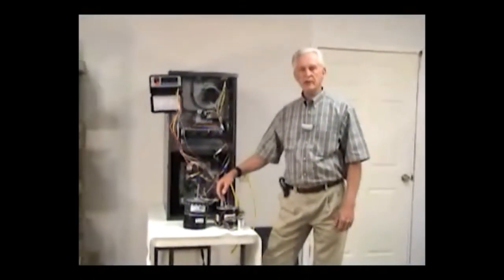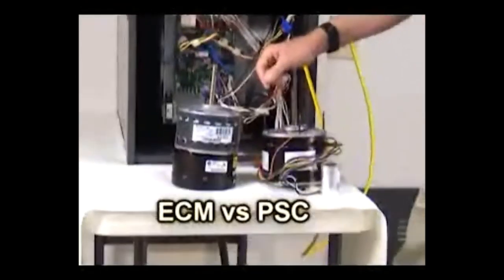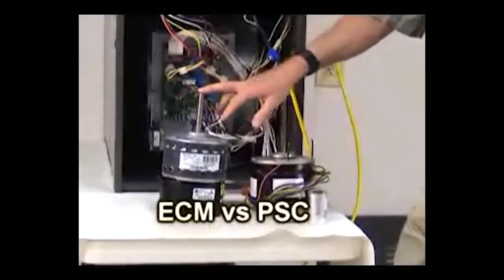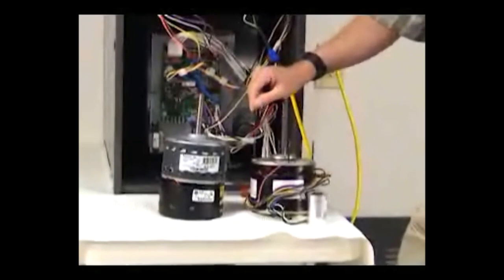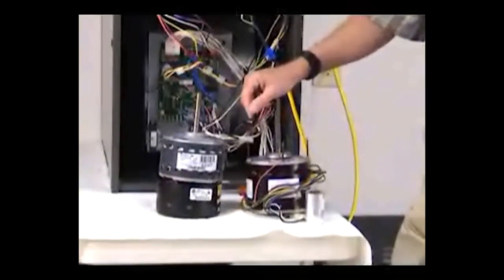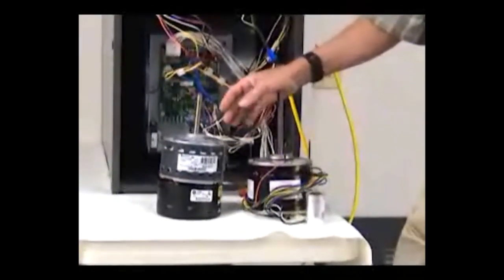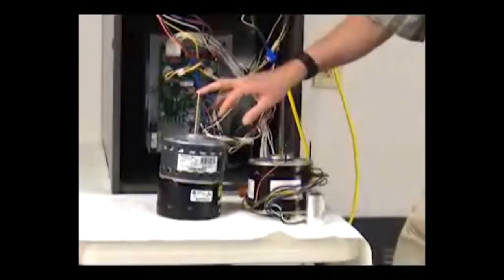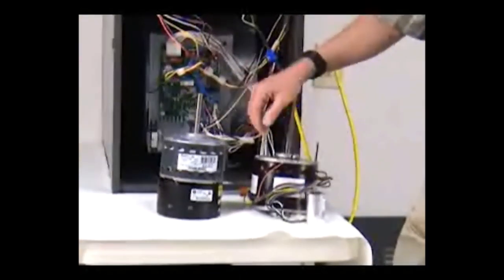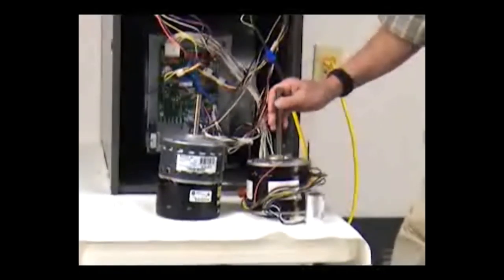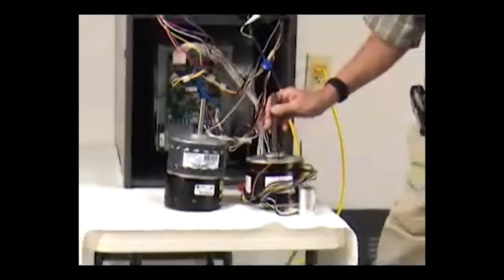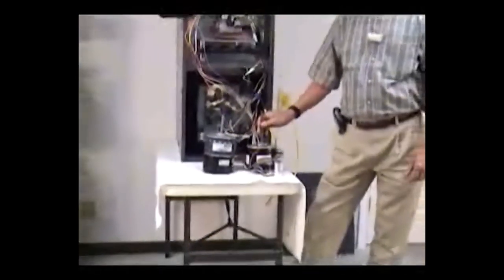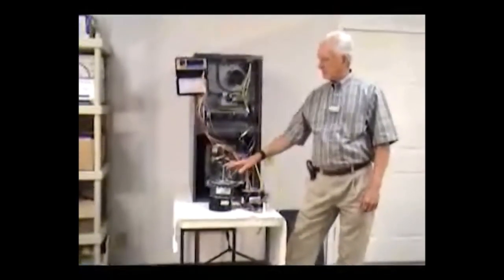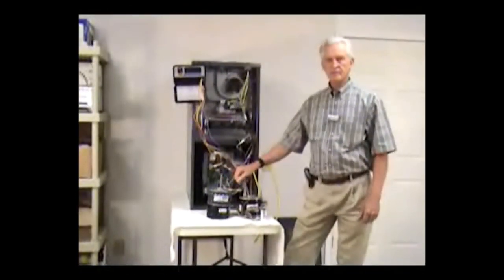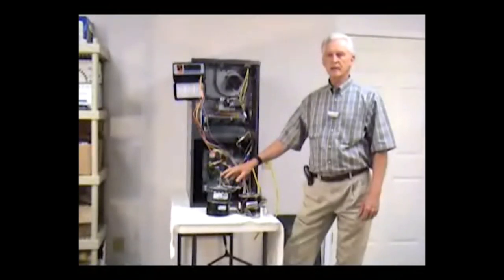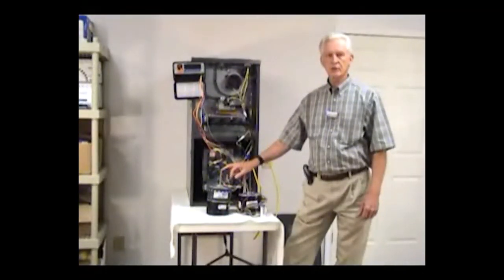But first, in the very first part of this DVD, I'd like to show you the difference and the operations of the ECM motor versus a split capacitor or PSC motor. And we will use those terms, ECM, for electronically commutated motors, or split capacitor motor, which would be a PSC motor. And to get the best gist of the ECM motor and its operation, it's probably a good idea to make a comparison between the two.